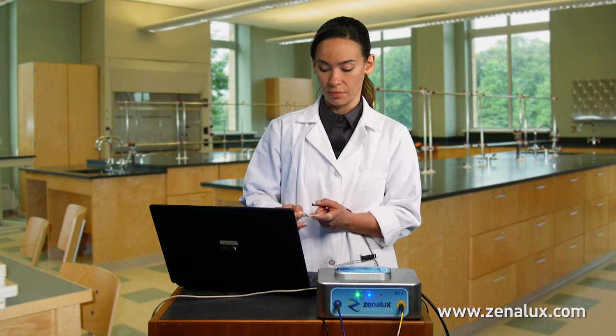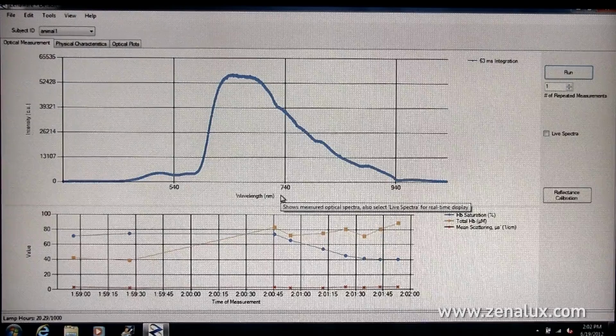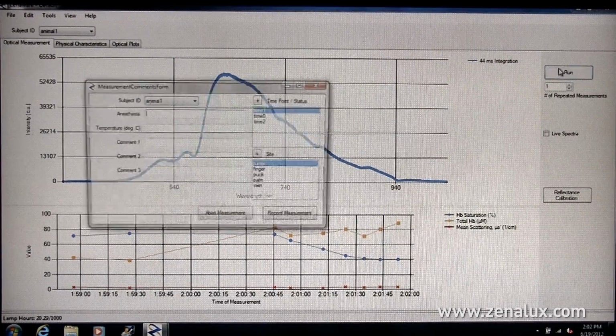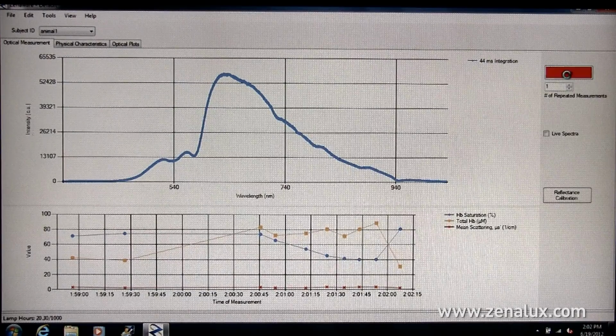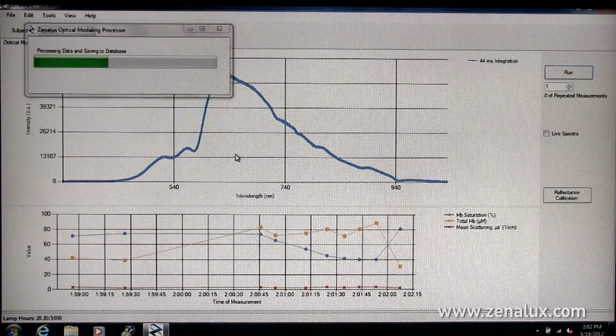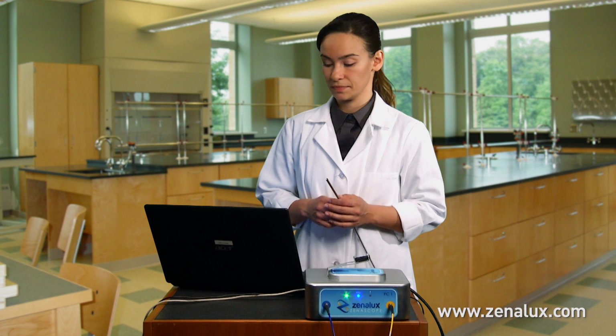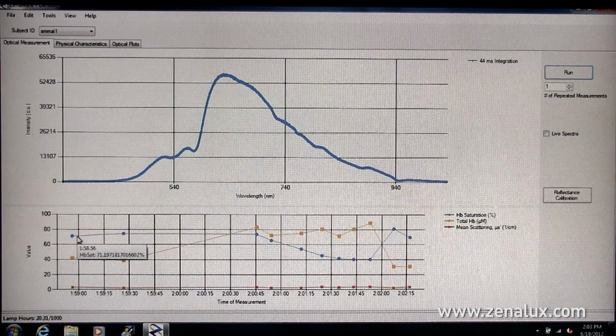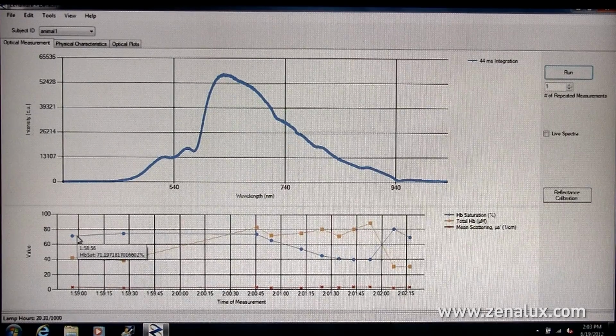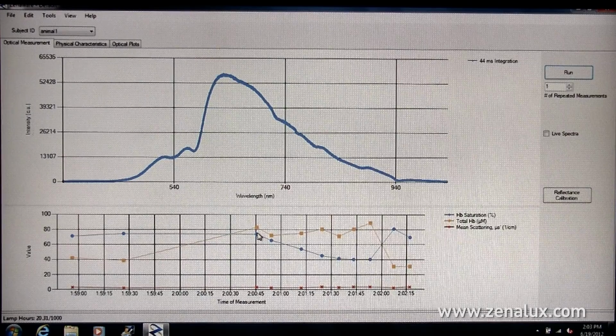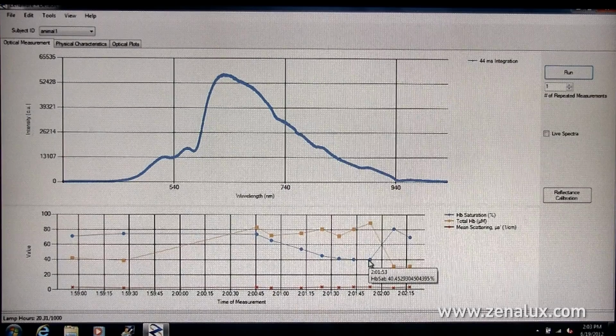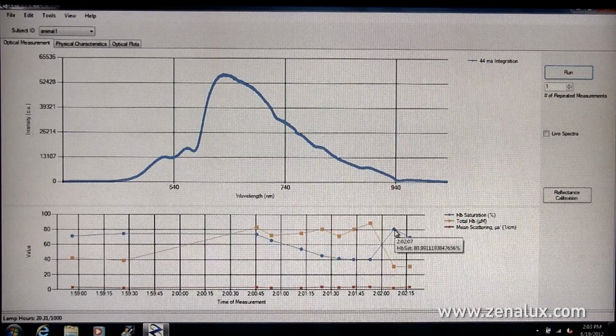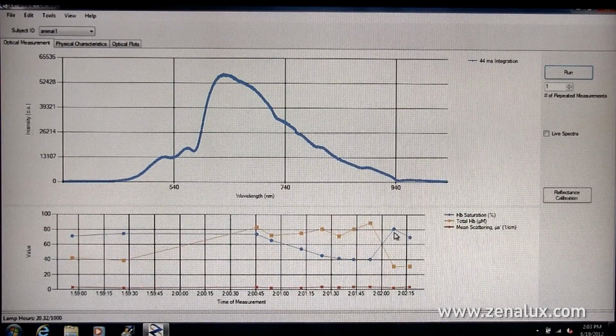Now I'm going to release the pressure on my fingertip and take a few additional measurements. So let's take a look at our data. All the way over to the left, we have our baseline measurements. What you can see is that the baseline measurement for hemoglobin saturation is quite high. The next point is the point at which I applied pressure to the system. As you can see, there's a significant drop in hemoglobin saturation over time. Once I release the pressure on my fingertip, hemoglobin saturation increases significantly.